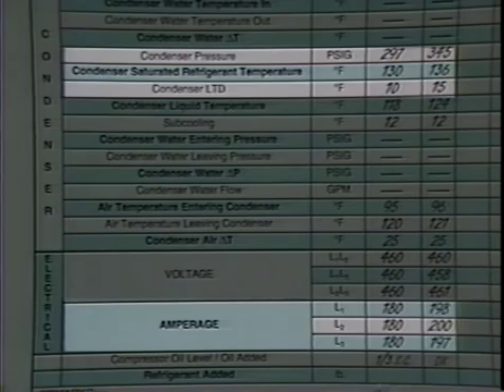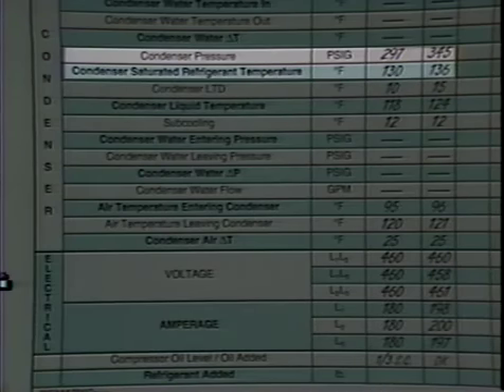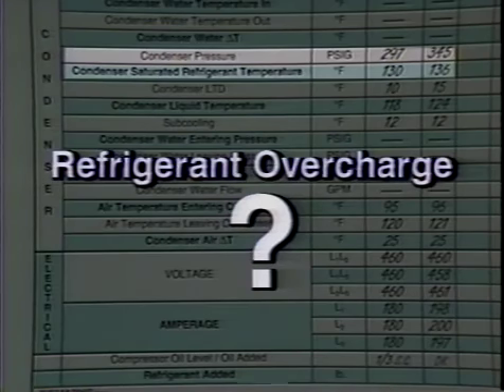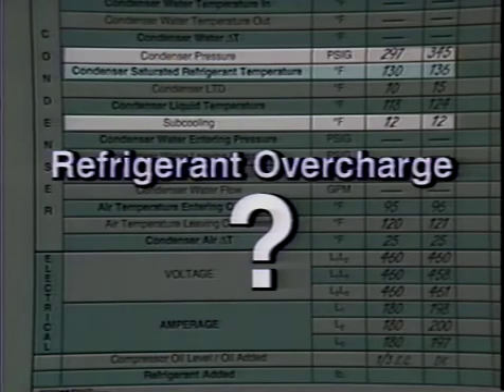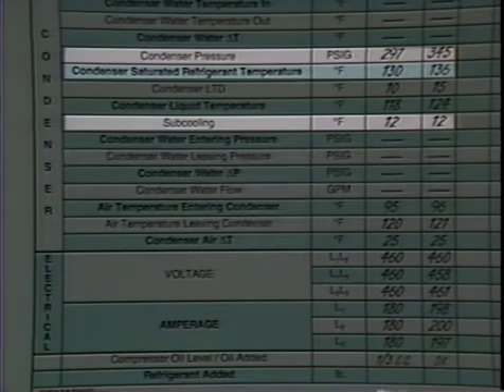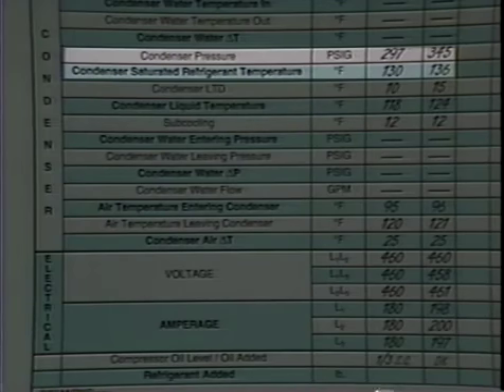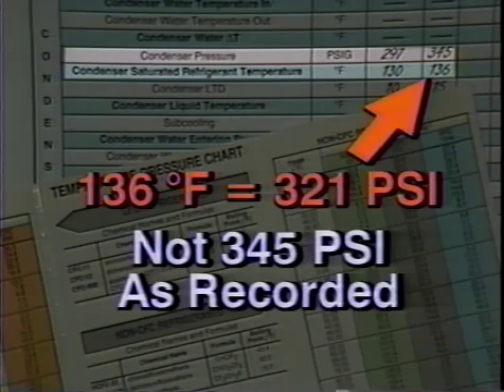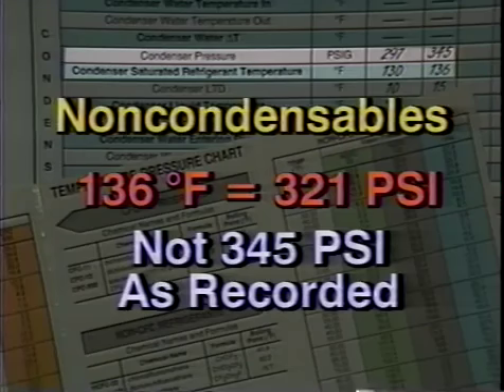One of the common causes of high condensing pressure and temperature is refrigerant overcharge. But remember that in that case, the liquid's subcooling increases. In this case, a check on subcooling shows it's at design with 12 degrees Fahrenheit. So we need to look still further. Comparing the pressure-temperature relationship, we see the condensing pressure does not correspond to the saturated liquid temperature, an indication of non-condensables in the condenser.